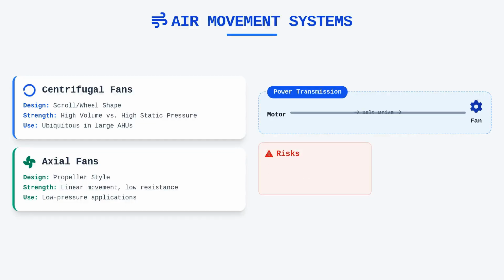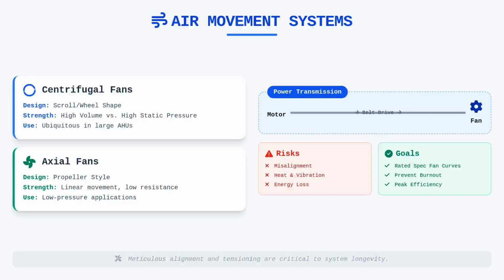When belts are loose or misaligned, the system loses efficiency and generates heat, and they also create a perfect environment for vibration issues. Proper maintenance of these mechanical parts ensures that the fan curves remain within the manufacturer's rated specifications, preventing motor burnout and excessive energy consumption.